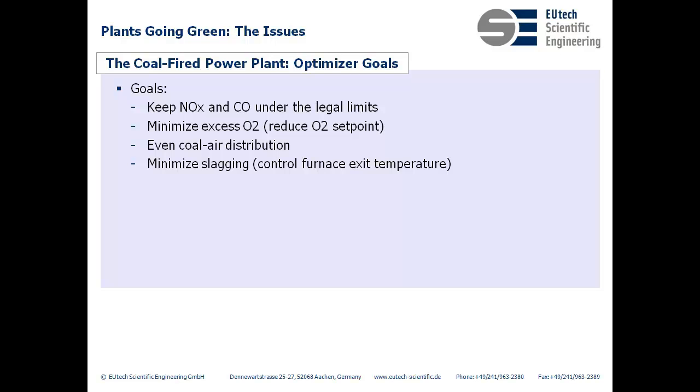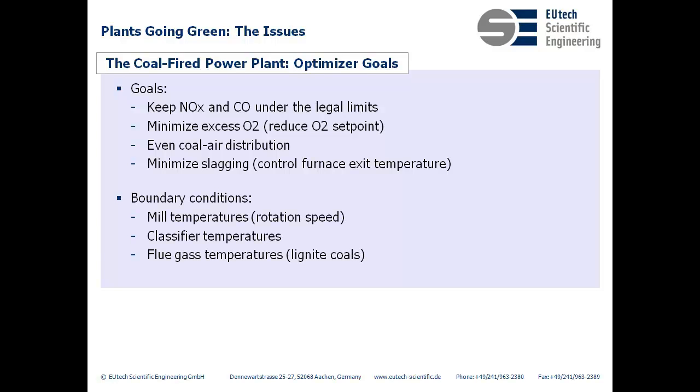Finally, high temperatures inside the boiler do mean more thorough combustion, but they can also lead to slagging. That's when ashes become soft and stick to the walls. So the optimizer needs to control the furnace exit temperature so it is high enough for thorough combustion but not too high that it leads to slagging.